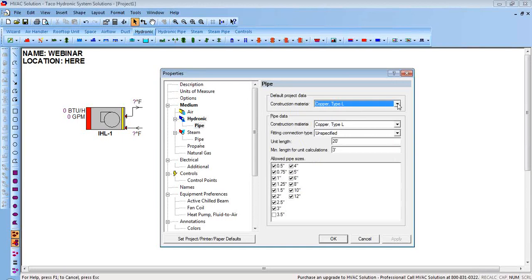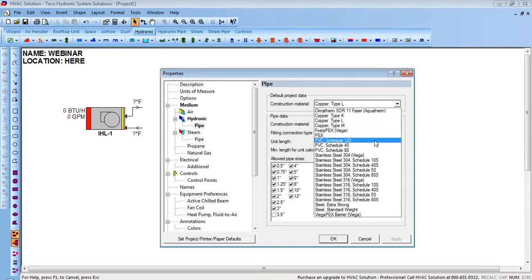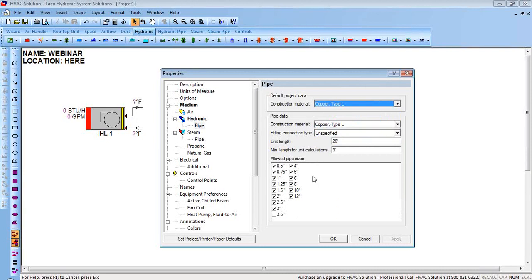Under piping, you can pick what kind of pipe you want to work with — I've got copper type L right now, but you can change it and every piece of pipe you put in will default to that type. If there's a certain pipe size you don't want, like 3.5-inch which is an oddball size that probably costs more than 4-inch, you can uncheck it so it won't use it on your job.